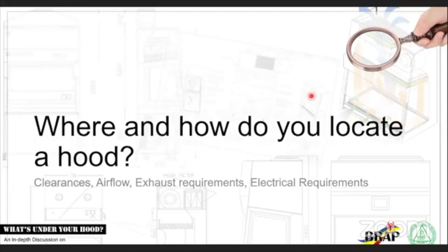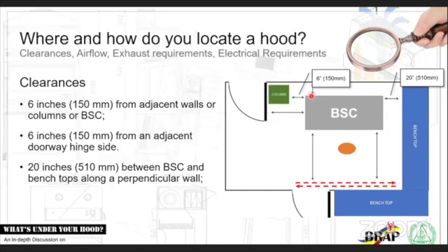Right? Again, clearances. These are the clearances for your biosafety cabinet: 6 inches from the back, 6 inches from the side, and 20 inches between biosafety cabinets and benchtops along a perpendicular wall. So we go through this first. You have a column here. You need to have 6 inches distance from this one, 6 inches from this one. This is a bigger one: 20 inches or 500 millimeters between biosafety cabinets on the side. So this would make room for people walking along this area.